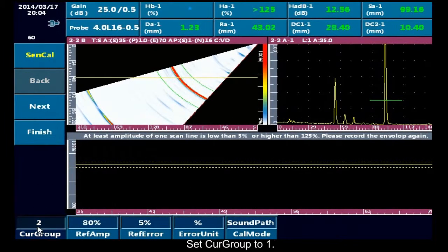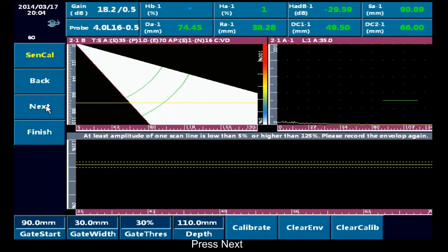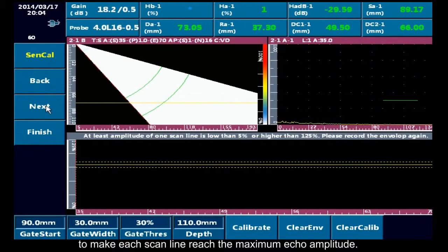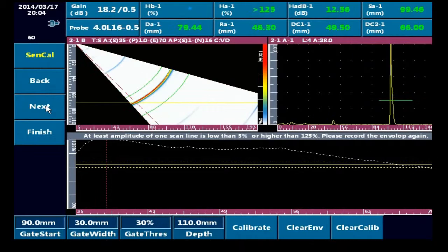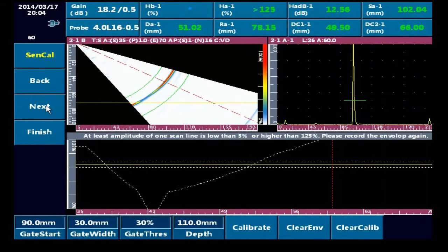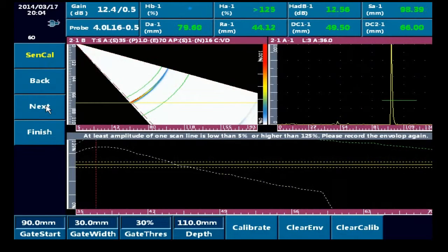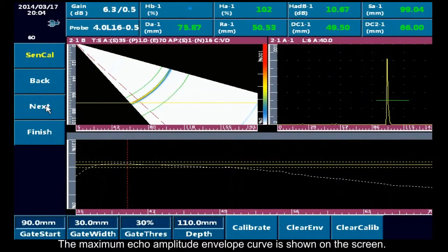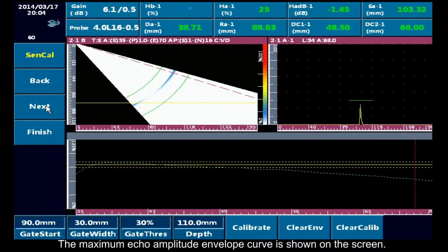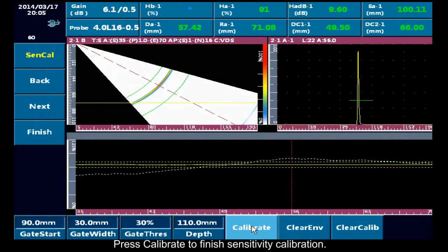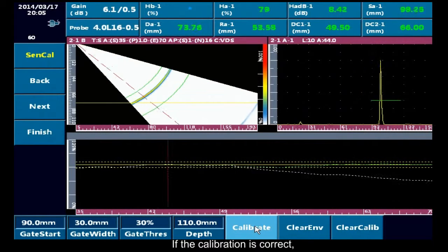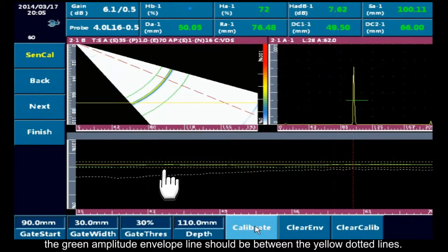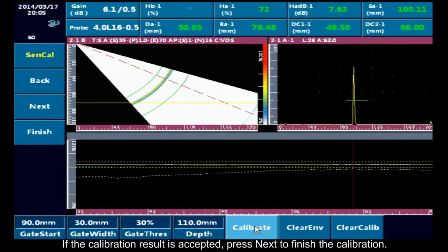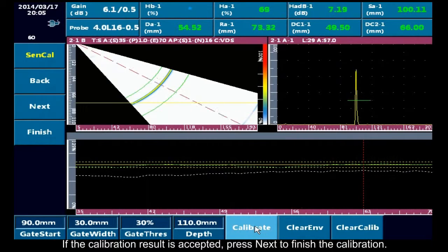Sensitivity calibration. Set CurGroup to 1. Press next. Put the probe on the test block. Move the probe forward and backward to make each scan line reach the maximum echo amplitude. The maximum echo amplitude envelope curve is shown on the screen. Press calibrate to finish sensitivity calibration. If the calibration is correct, the green amplitude envelope line should be between the yellow dotted lines. If the calibration result is accepted, press next to finish the calibration.